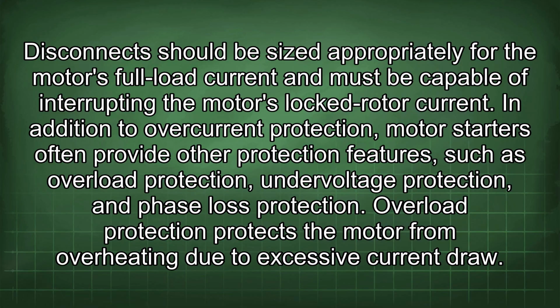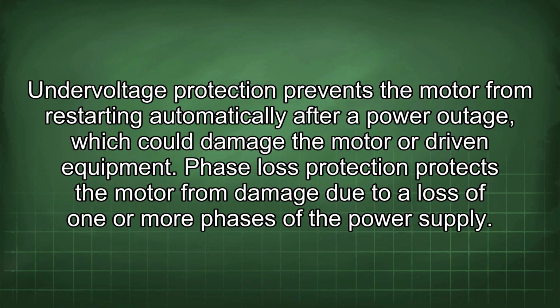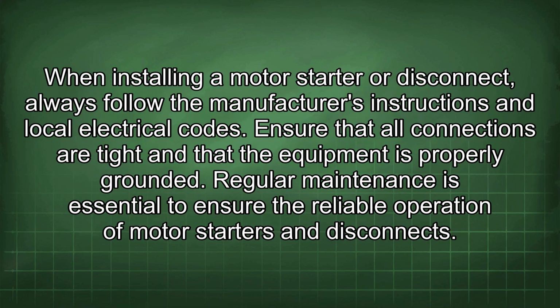and phase loss protection. Overload protection protects the motor from overheating due to excessive current draw. Undervoltage protection prevents the motor from restarting automatically after a power outage, which could damage the motor or driven equipment. Phase loss protection protects the motor from damage due to a loss of one or more phases of the power supply. When installing a motor starter or disconnect, always follow the manufacturer's instructions and local electrical codes.